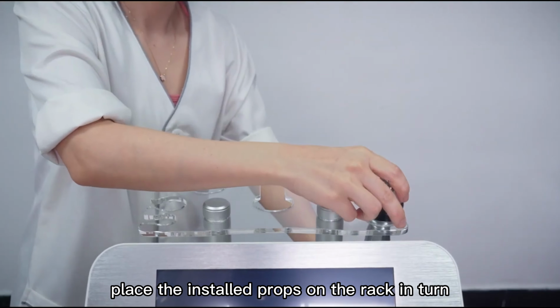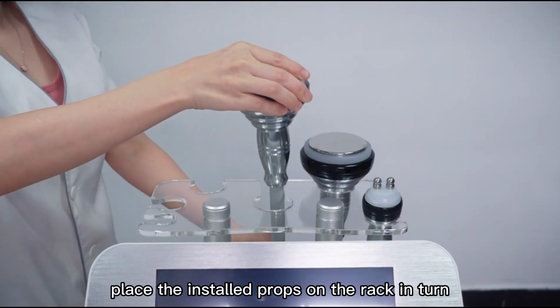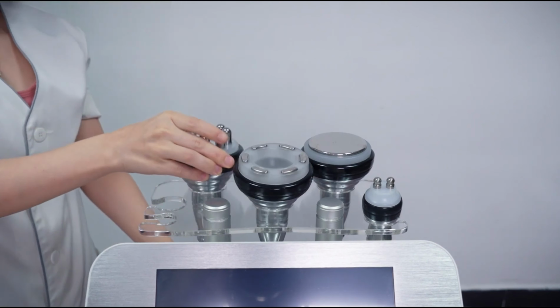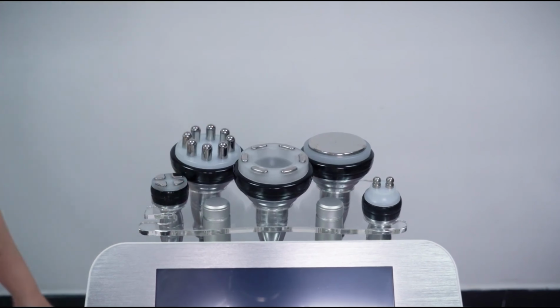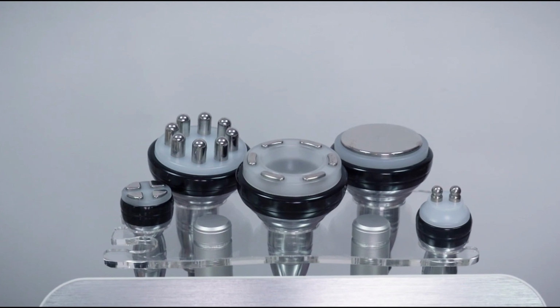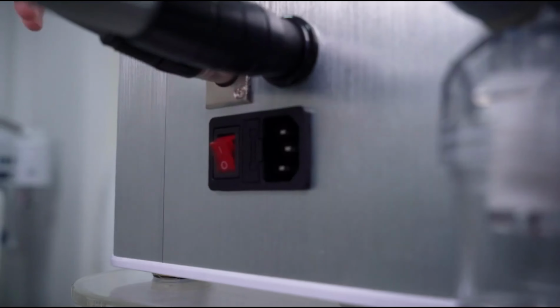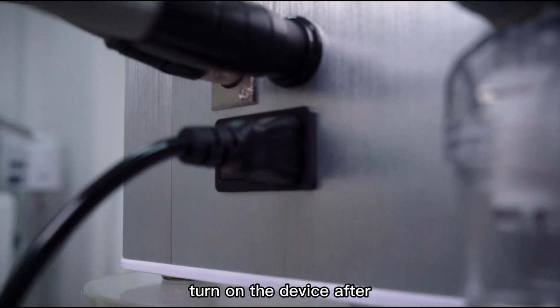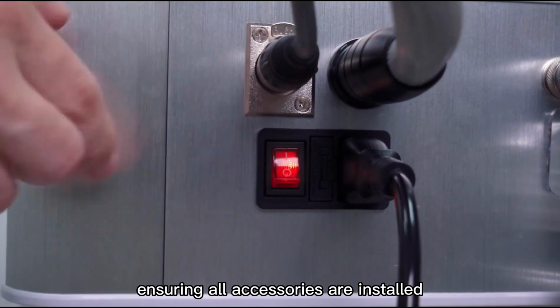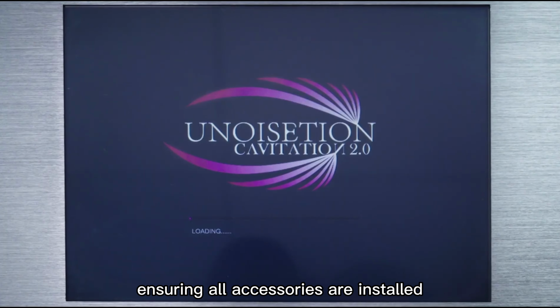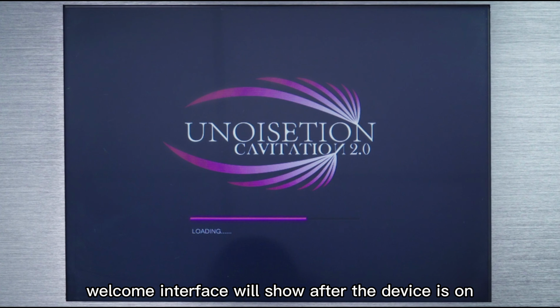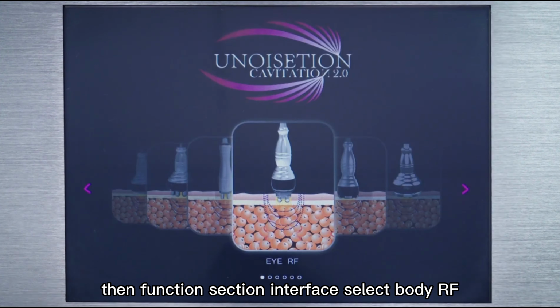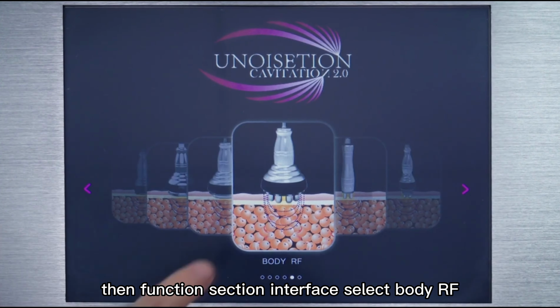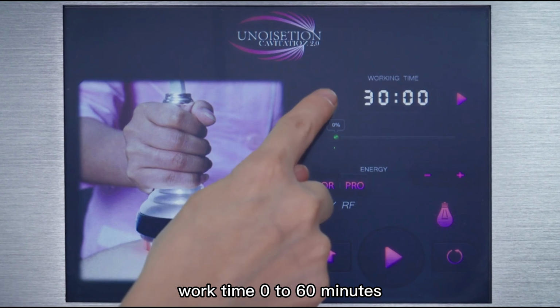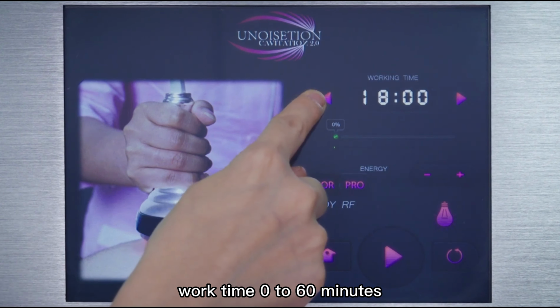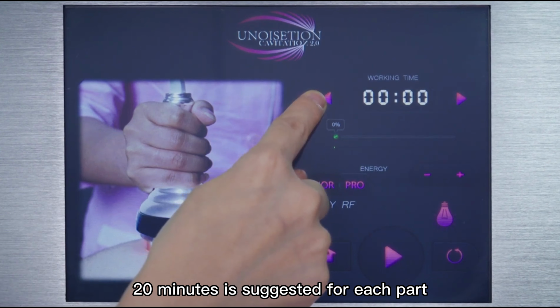Place the installed props on the rack in turn. Install power cable. Turn on the device after ensuring all accessories are installed. Welcome interface will show after the device is on. Then function section interface. Select body RF. Work time 0 to 60 minutes. 20 minutes is suggested for each part.